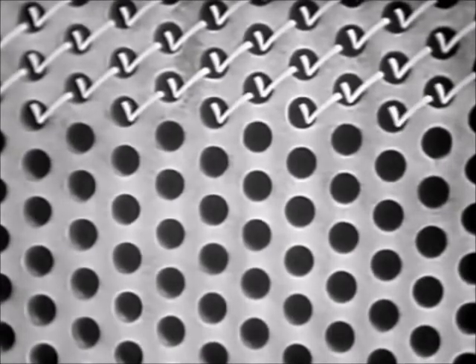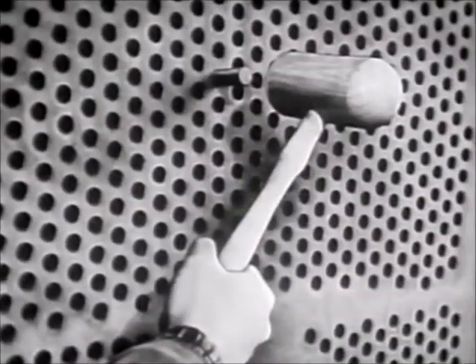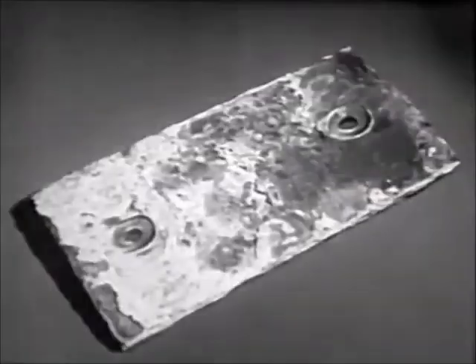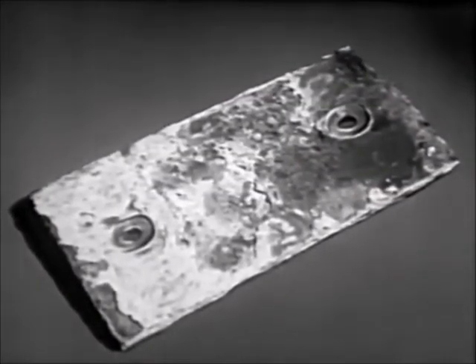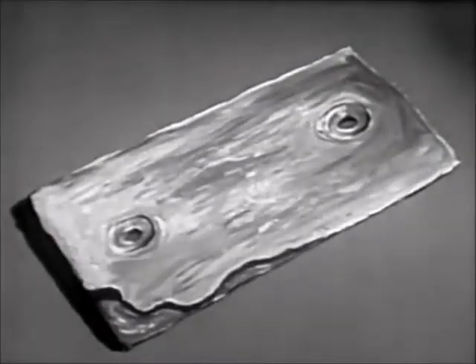Because condensers have such a large number of tubes, cleaning and inspection must be done according to an orderly plan, so no tubes will be missed. When you find a defective tube, mark it with a plug so you can find it later for repair. Inspect the zincs, too. Corrosion forms a crust which stops the zinc's protective action. When you remove the crust, you often find that a new zinc is needed.